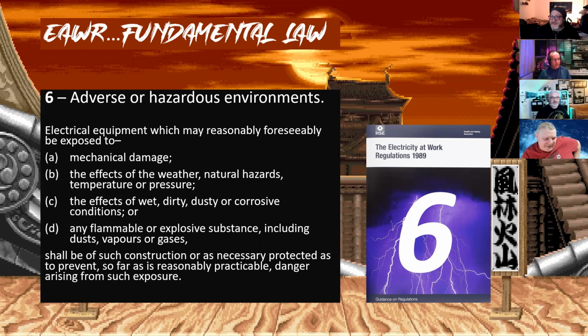Adverse or hazardous environments - electrical equipment which may reasonably foreseeably be affected. This is part of due diligence. If you can foreseeably and reasonably see that this stuff's going to happen, then you need to protect against mechanical damage, the effects of weather, natural hazards becoming more of a thing, temperature, pressure, wet, dirty, dusty, corrosive. This is all external influences, guys, this is bread and butter stuff.